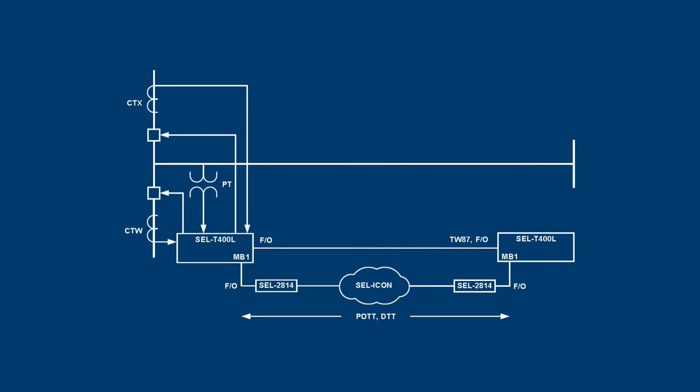Now that we've completed the communication settings, let's take a closer look at our application. We're protecting a 120-mile, 500 kV line terminated on two breakers with bushing CTs having 800 to 5 and 1,000 to 5 ratios. The CT ratios are therefore 160 and 200 respectively.